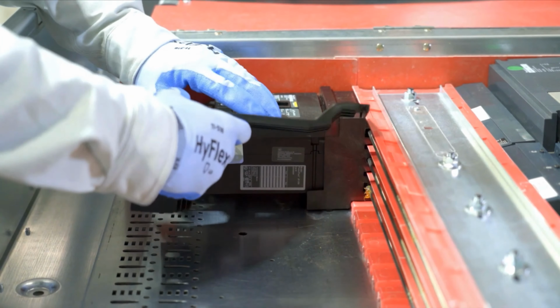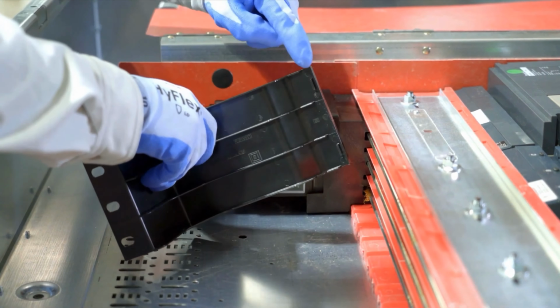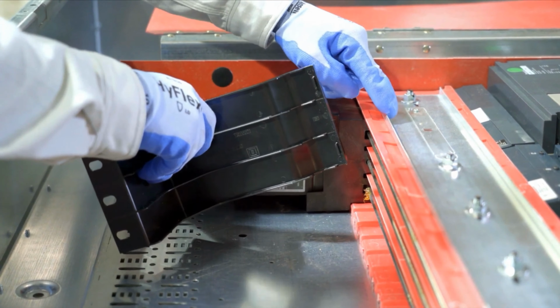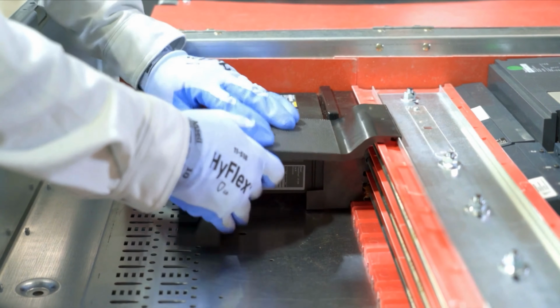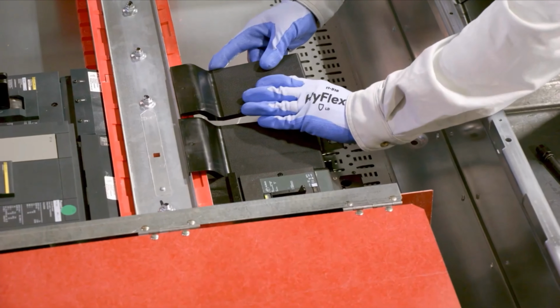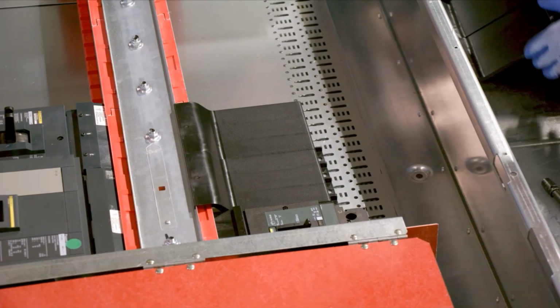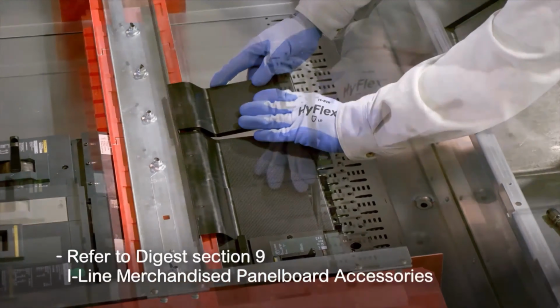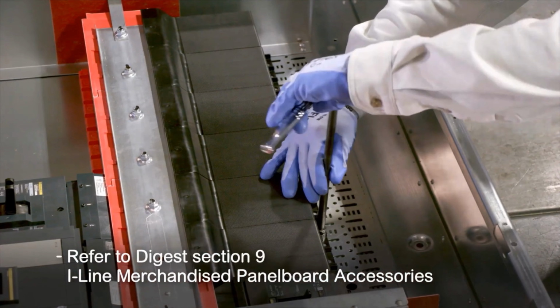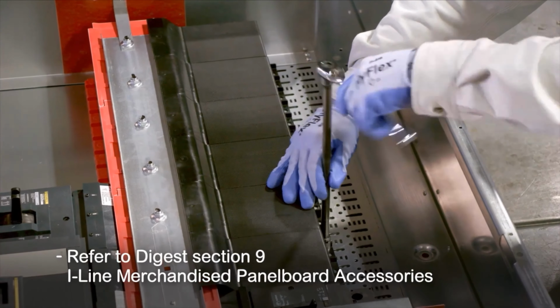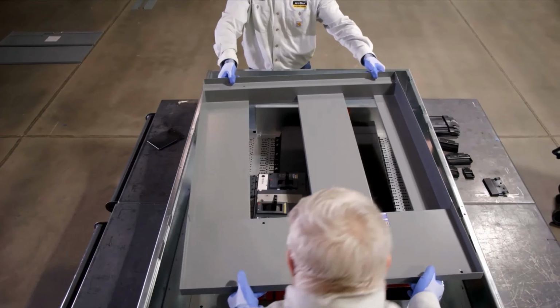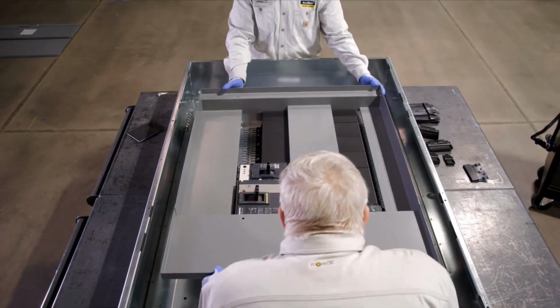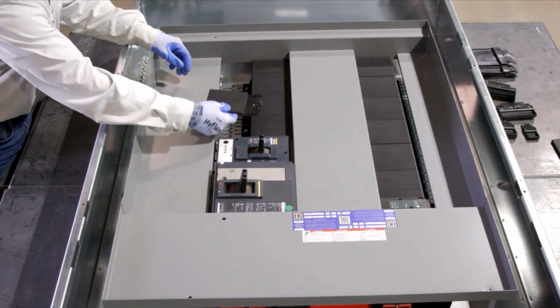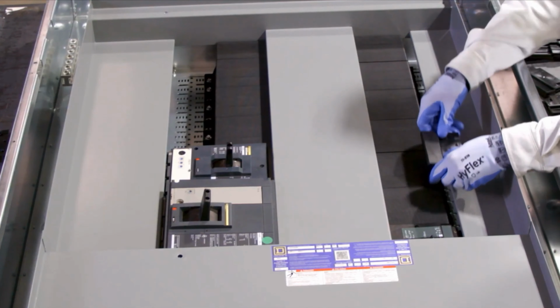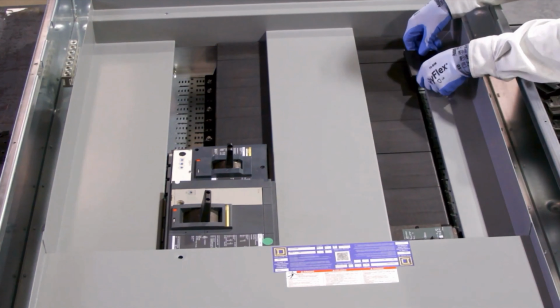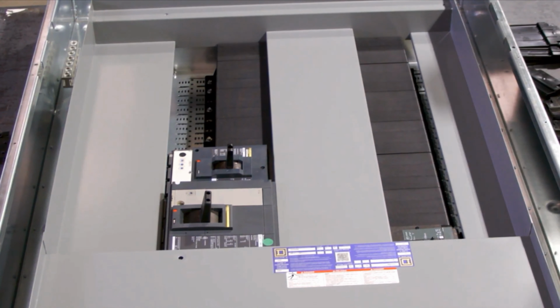Blank fillers should be mounted over unused areas of the I-line panel board. To install blank fillers, simply mount on the mounting pan like this. The blank fillers must be screwed to the back pan with the included hardware. Refer to Digest Section 9, I-line Merchandised Panel Board Accessories for which blank extensions to use with which breakers. Perform a test fit of the interior dead front to determine how many blank extensions will be needed to cover the exposed bus area. All unused bus spaces must be covered by blank extensions.